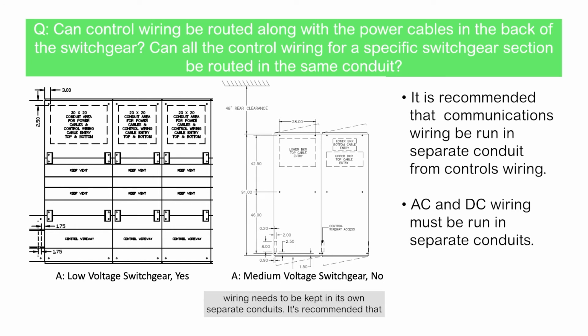It's recommended that any communications wiring, whether it's Cat5 cable, fiber, or RS-485 wiring, be run into a separate conduit from all the other control wiring, the AC and DC wiring.